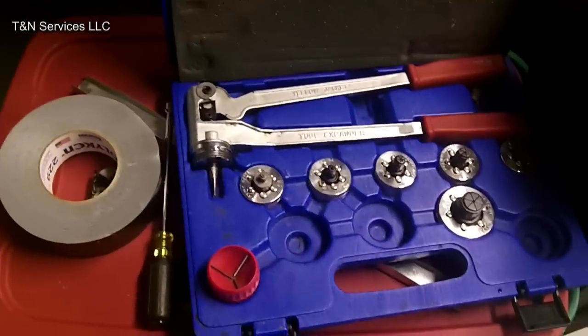Alright, so I got the coil in place, and this actually is a replacement coil. It was leaking at one time and has been replaced. I don't know when, but I can tell because it's missing the horizontal drain pan that normally comes in the old Goodmans, and this little piece was cut out there. So this is a replacement coil. I took my swedger, swedged it, and brazed it in. There's my swedger, or my expander, sorry.